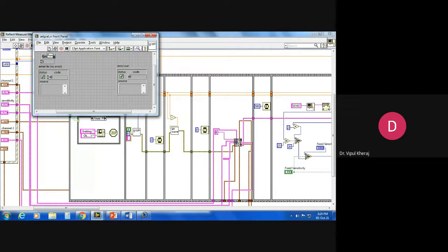And you will also be able to see the spectrum widen in grating 2 because of the bigger grooves. Now if I change it to grating 1 again, you see the grating is slowly revolving, and that motor is calibrated to precisely position it so that the wavelength of the desired value coincides with the outer slit. Okay, so now we are back to grating 1, right?